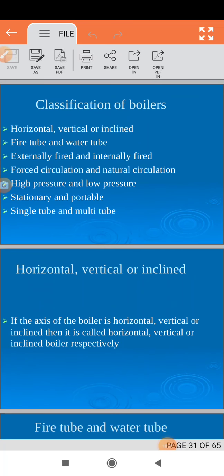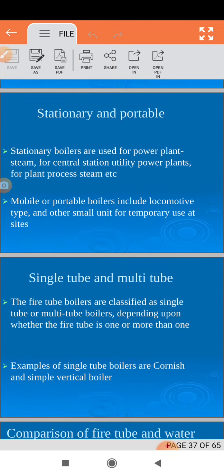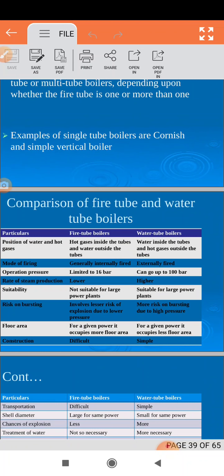Now another important thing is the difference between fire tube and water tube boiler. There are a few parameters to differentiate them. First point: position of water and hot gases. In the fire tube boiler, hot gases are inside the tube and water surrounds the tube. In the water tube boiler, water is inside the tube and hot gases are outside. Regarding modes of firing: generally fire tube boilers are internally fired and water tube boilers are externally fired.